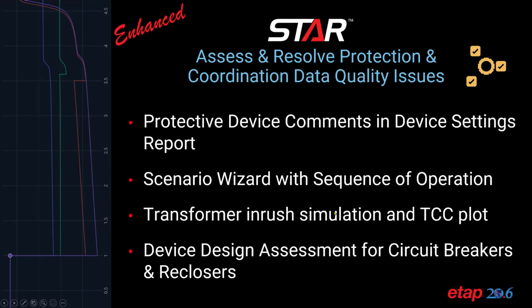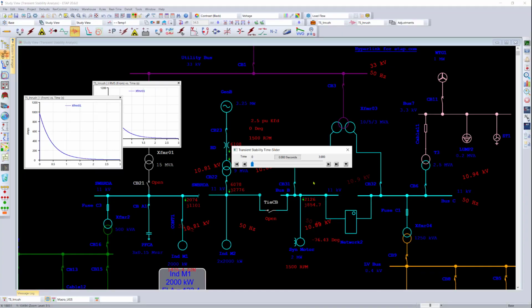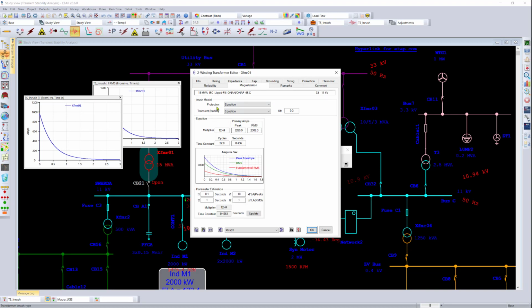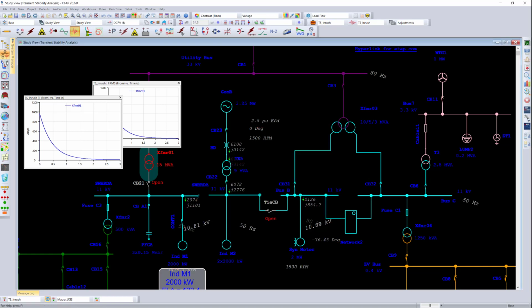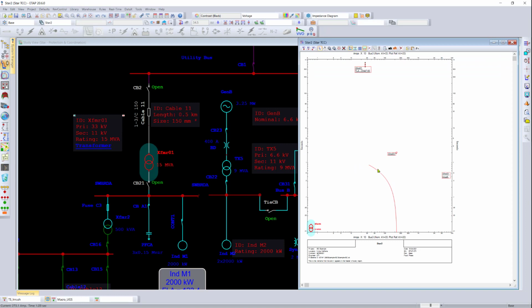Since we were talking about transformer inrush, let's look at transformer inrush simulation and the TCC plot. Since the equation-based calculation is new in ETAP 20.6, you can simply go inside the transformer magnetization page. Again, make sure that the protection is using equation, piecewise, or point. If you're using equation-based, you can simply evaluate the parameters, look at the multipliers and the time constant decays. Remember this value, 12.44, and we can essentially go into Star and plot the transformer inrush curve onto our TCC.